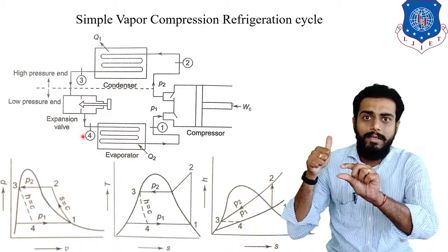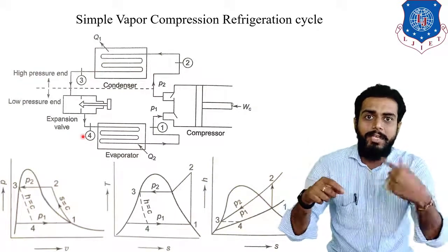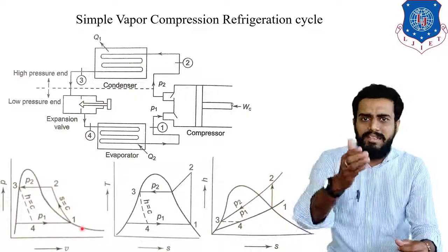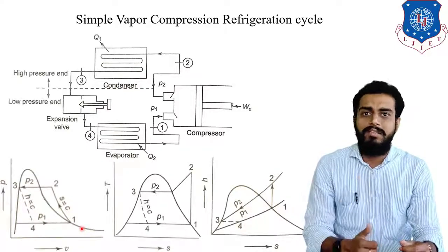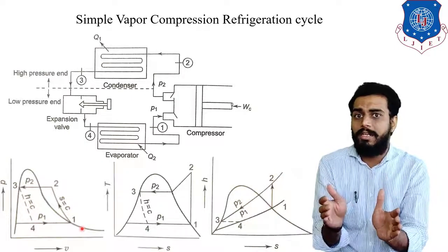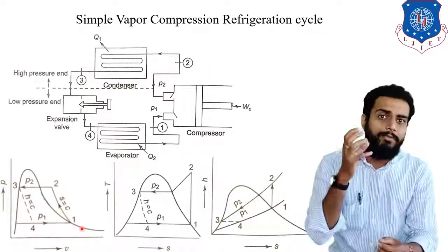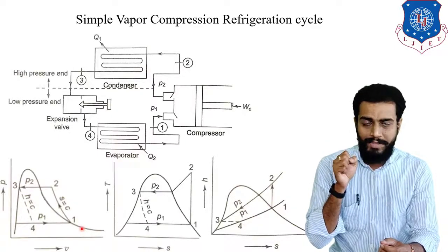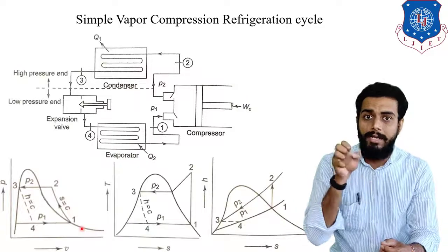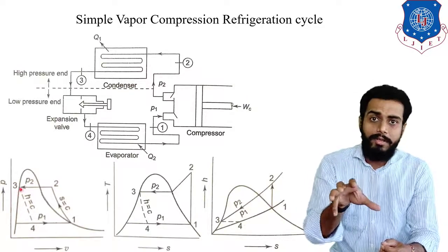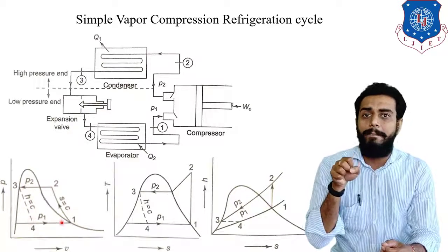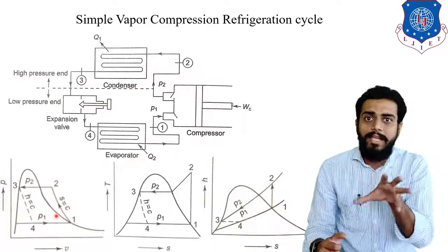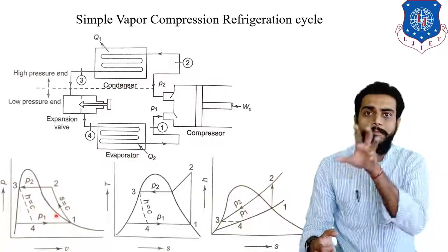So what will happen? Simple. The refrigerant will start evaporating immediately. Now, sir, what is the advantage of doing so? The advantage is simple, students. The whole liquid refrigerant will absorb, because if you want to convert liquid into vapor, you have to absorb the latent heat, and latent heat is somewhat higher compared to the sensible heat. Due to that latent heat, wherever the refrigerant passes, it will absorb the heat around itself or around the tubes.